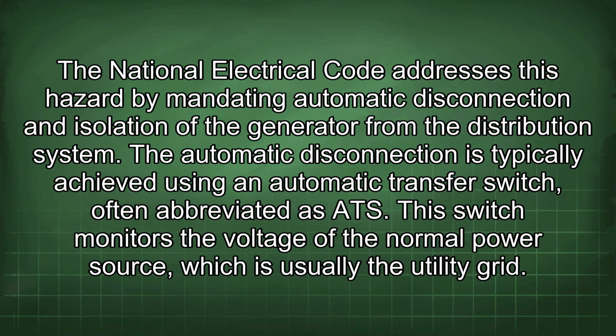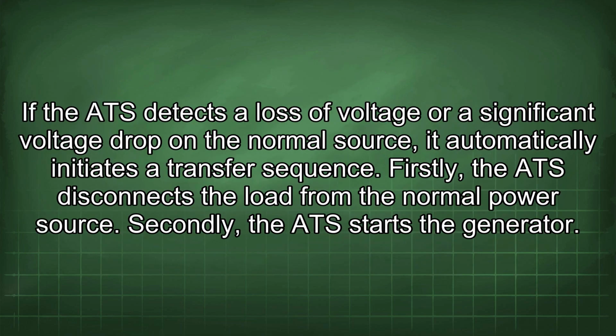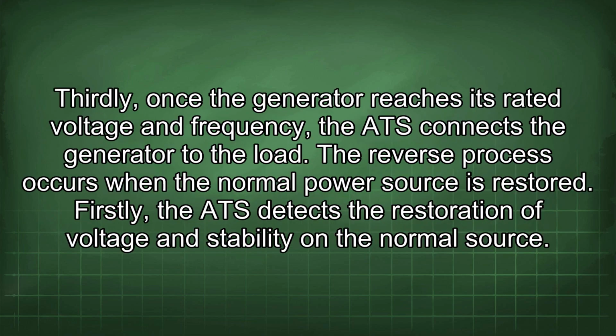This switch monitors the voltage of the normal power source, which is usually the utility grid. If the ATS detects a loss of voltage or a significant voltage drop on the normal source, it automatically initiates a transfer sequence. Firstly, the ATS disconnects the load from the normal power source. Secondly, the ATS starts the generator. Thirdly, once the generator reaches its rated voltage and frequency, the ATS connects the generator to the load.